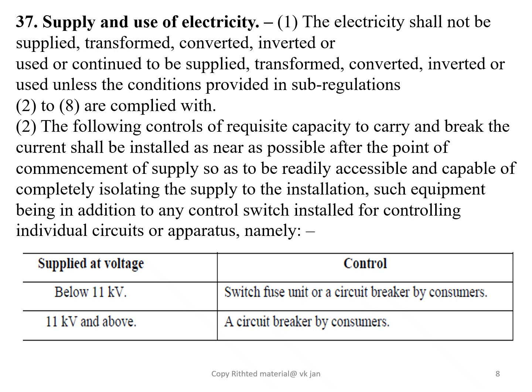I'm not giving all the rules. Rule 2 is important. The following controls of requisite capacity to carry and break the current shall be installed as near as possible after the point of commencement of supply, so as to be readily accessible and capable of completely isolating this supply to the installation, such equipment being in addition to any control switch installed for controlling individual circuits or apparatus, namely below 11 kV, switch fuse units, or alternatively circuit breaker by consumer, and above 11 kV, a circuit breaker by consumer.